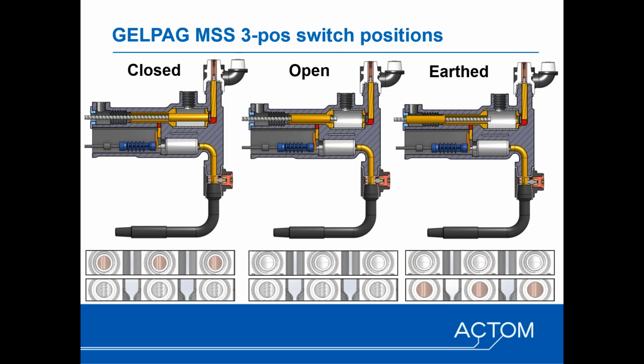Looking at the top part, I don't know if you can see my mouse, the top section is the 3-position switch, sometimes referred to as the DES or disconnecting earthing switch, and the bottom section is the vacuum interrupter or the circuit breaker portion. They are connected in series to form effectively the incomer or feeder, otherwise known as the branch circuit.